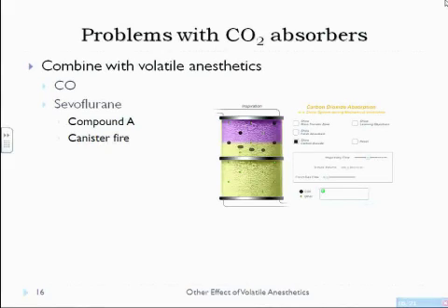Now, there are some recent problems that we've seen with CO2 absorbers. CO2 absorbers combined with volatile anesthetics, especially if they're dry, will form carbon monoxide. All of them will do that. Sevoflurane is unique in the sense that its metabolism by the strong base leads to the formation of compound A. And it has also been found recently to possibly increase the risk of developing a canister fire.